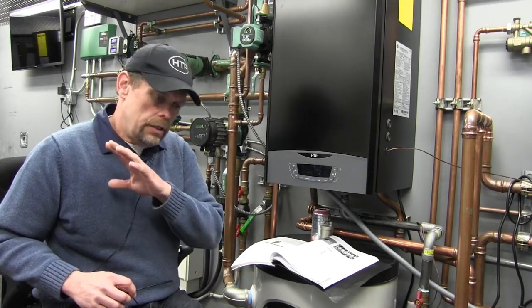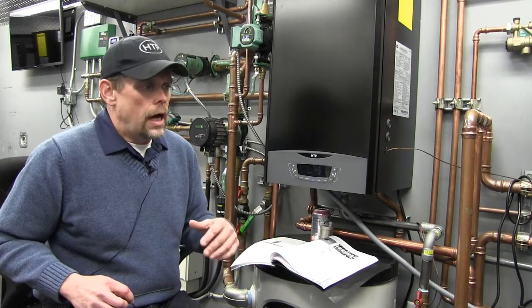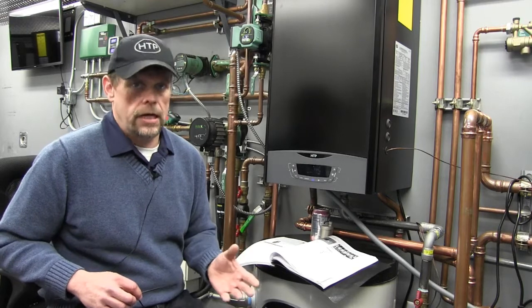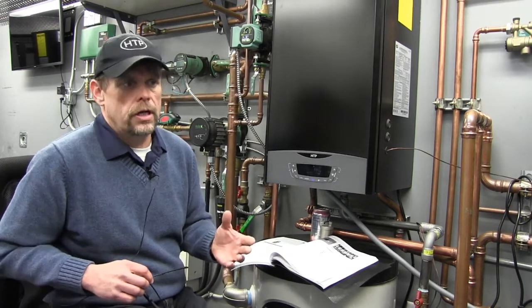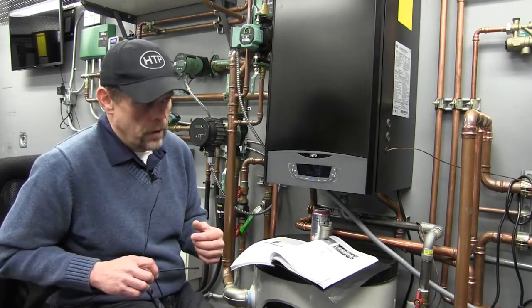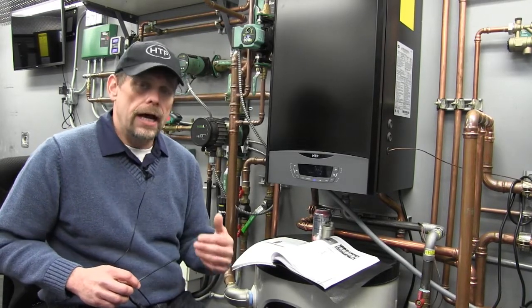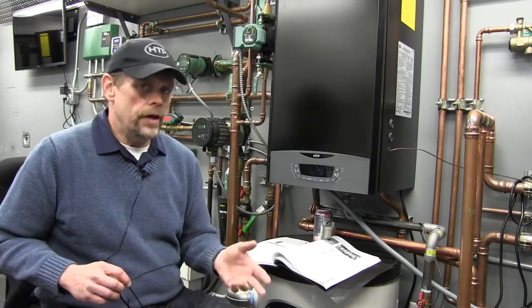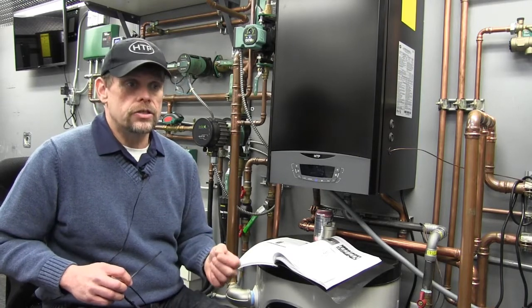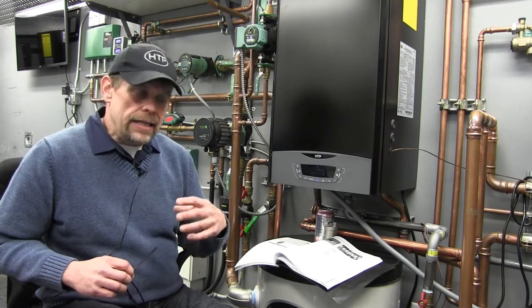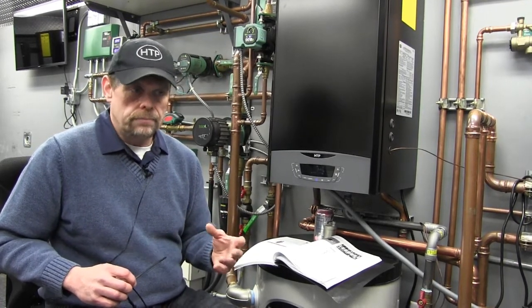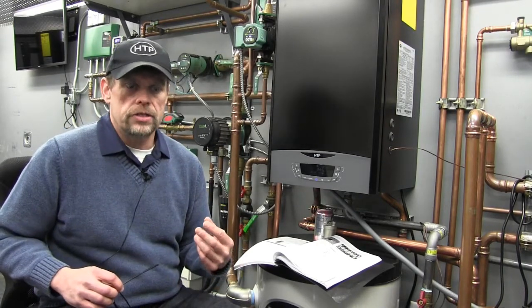At 190 degrees, the burner will shut off, the circulator pump will stay running. If it exceeds 190 degrees, if for any crazy reason the burner is running away, there will be a hard lockout at 210 degrees. Somebody will have to go and rectify the situation and do a manual reset if the boiler temperature had got that far. Now, set point temperature. The cutoff, the burner off cycle, is going to vary based on how long the burner has been running since flame had been established. The theory is to eliminate or minimize short cycling. So in other words, the cutoff point is going to vary based on how long the burner is running, but it will never exceed 7 degrees above set point. So it's important to understand the difference between set point, limit, and lockout. I hope that has made it a little clearer.